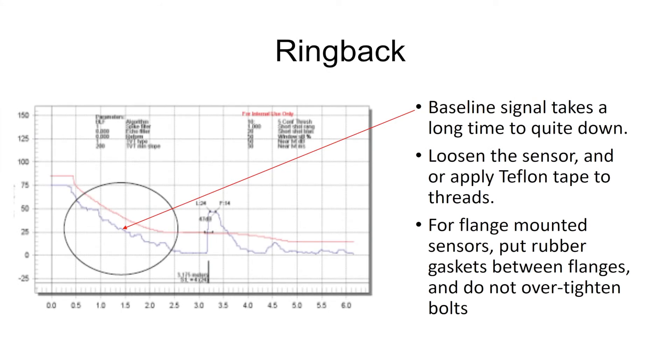So how do we take care of ringback? If the sensor is thread mounted, I want to loosen it so it's just barely hand tight. If necessary, put a couple layers of Teflon tape around the threads. For a flange mount, take the sensor off the flange, put one or two rubber gaskets between the vessel flange and the sensor flange, and just hand tighten the bolts if you can. I want to get rid of that acoustic coupling between the sensor and what it's mounted to.